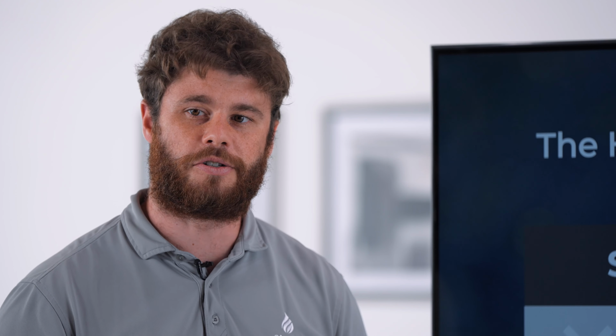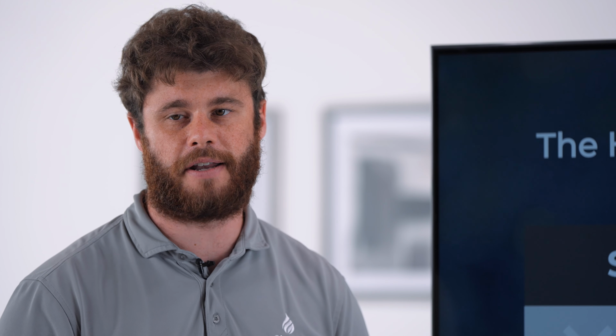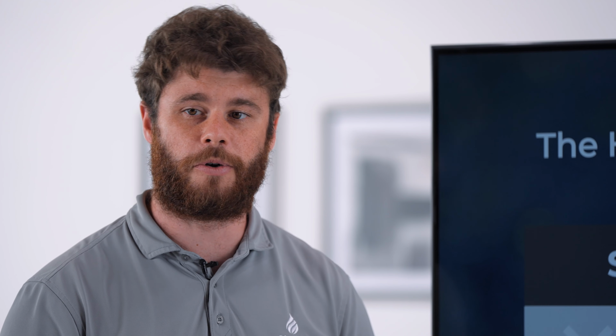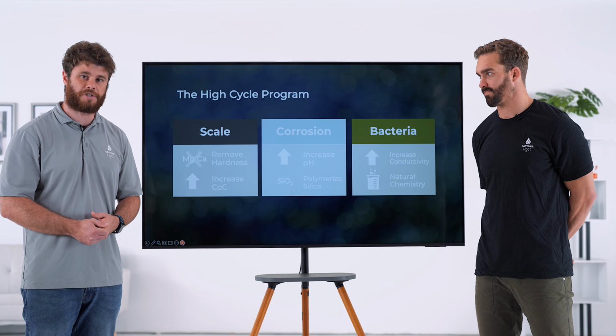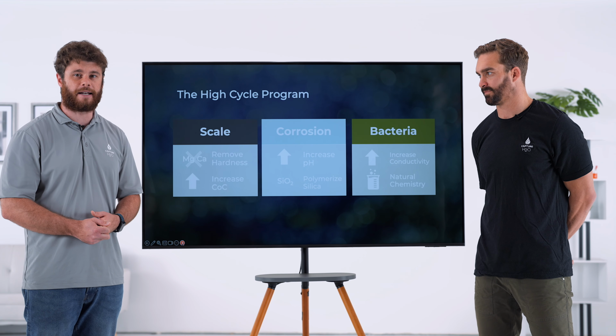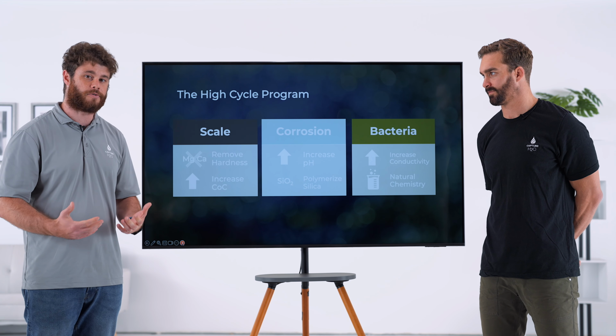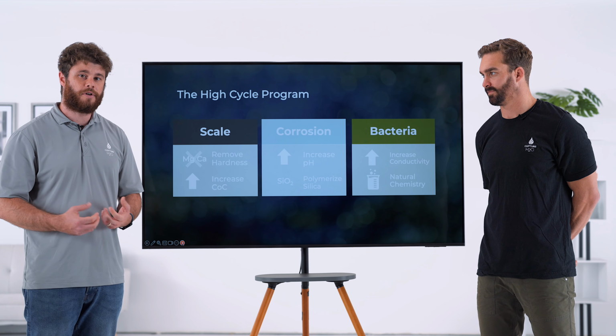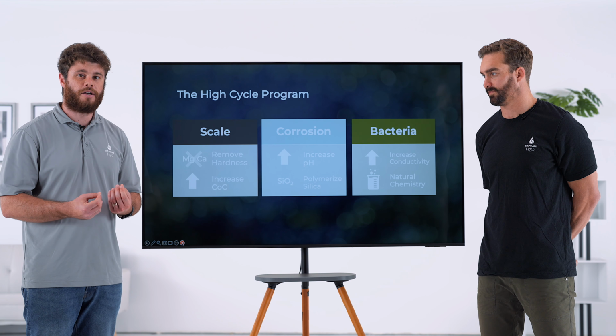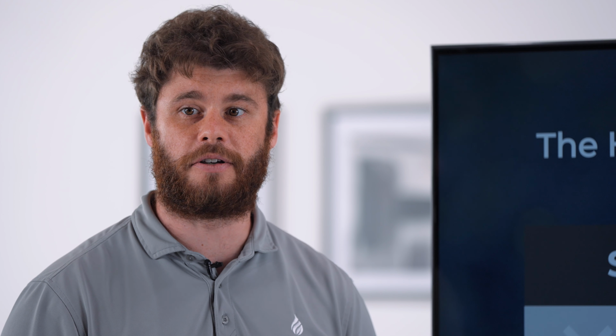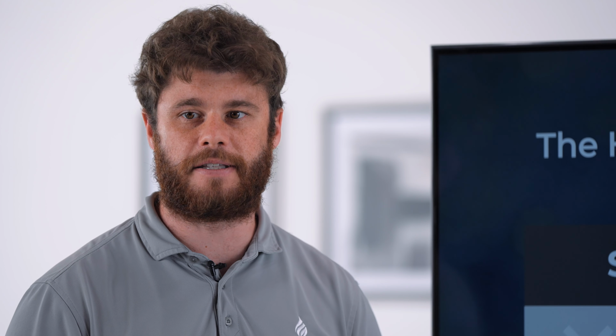When we install our softeners on the makeup line to the cooling tower, we redirect 100% of the makeup water through our pretreatment system, removing 100% of the scaling ions, magnesium and calcium, which are the building blocks for scale. When you remove these scaling minerals from the water, we can begin to increase cycles in the cooling tower without risking scaling tendencies in the tower itself.